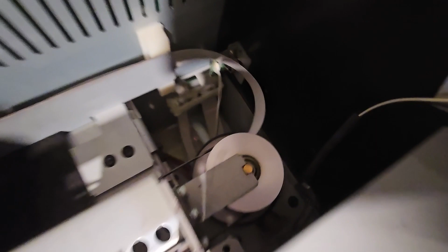Your scan motor is behind the control panel here. You remove the screws and you'll get to the scan motor. Your problem definitely could be the scan motor is bad. It could be that there's too much tension on this wire. I'll go ahead and stop this real quick, show you this wire.